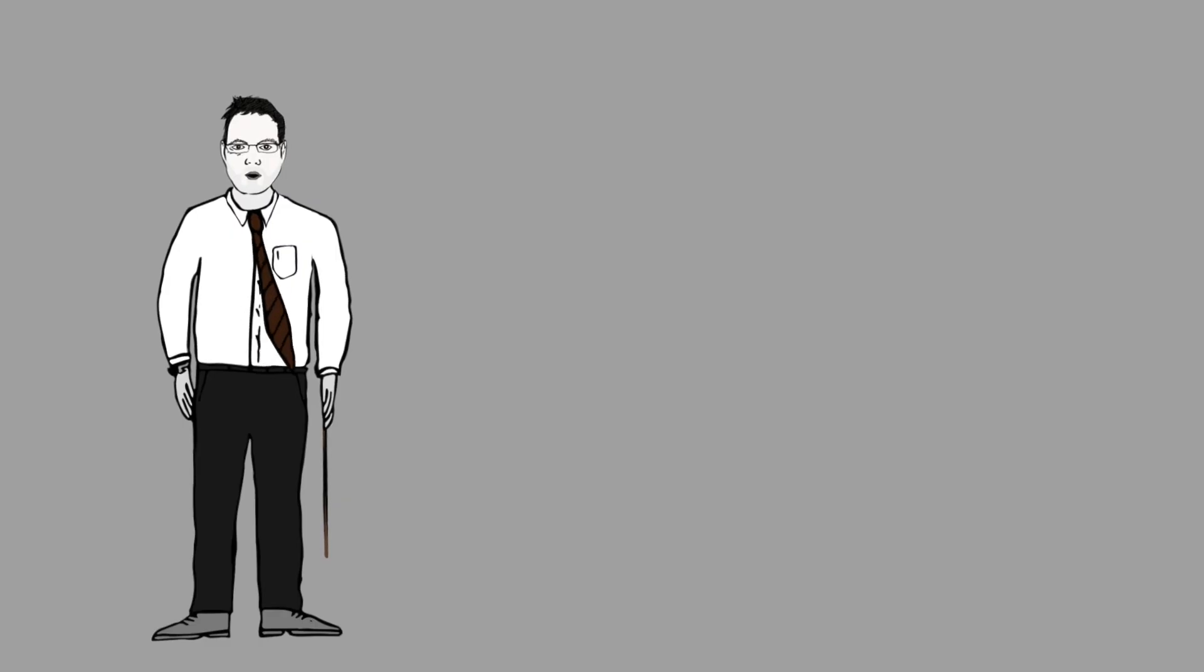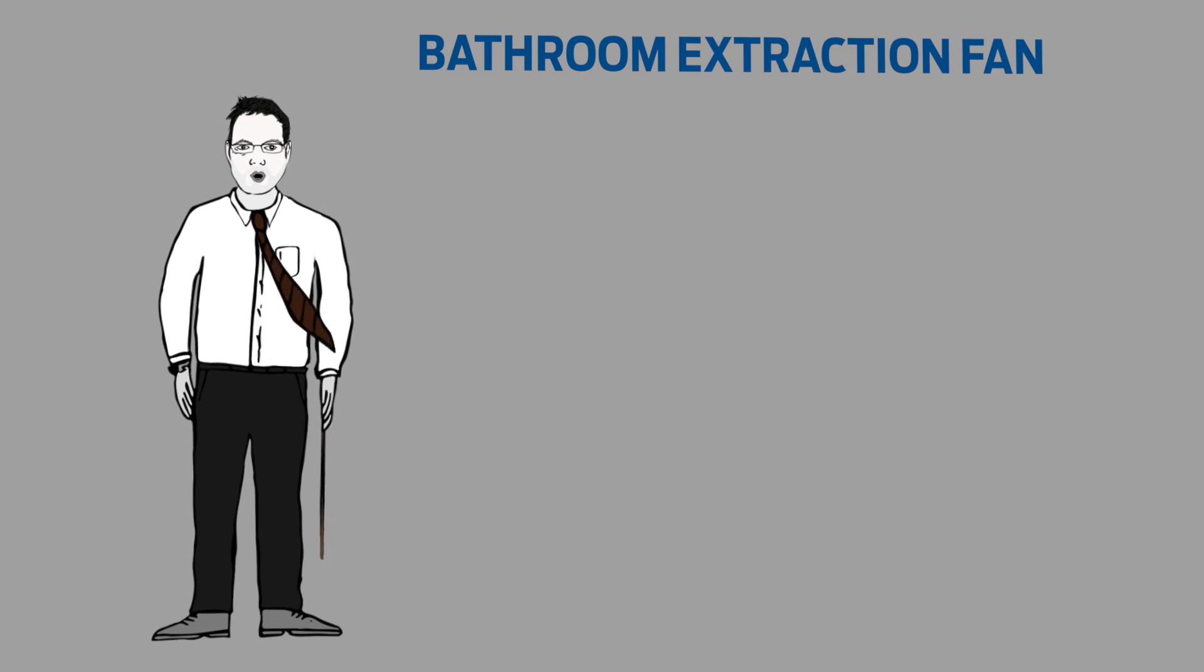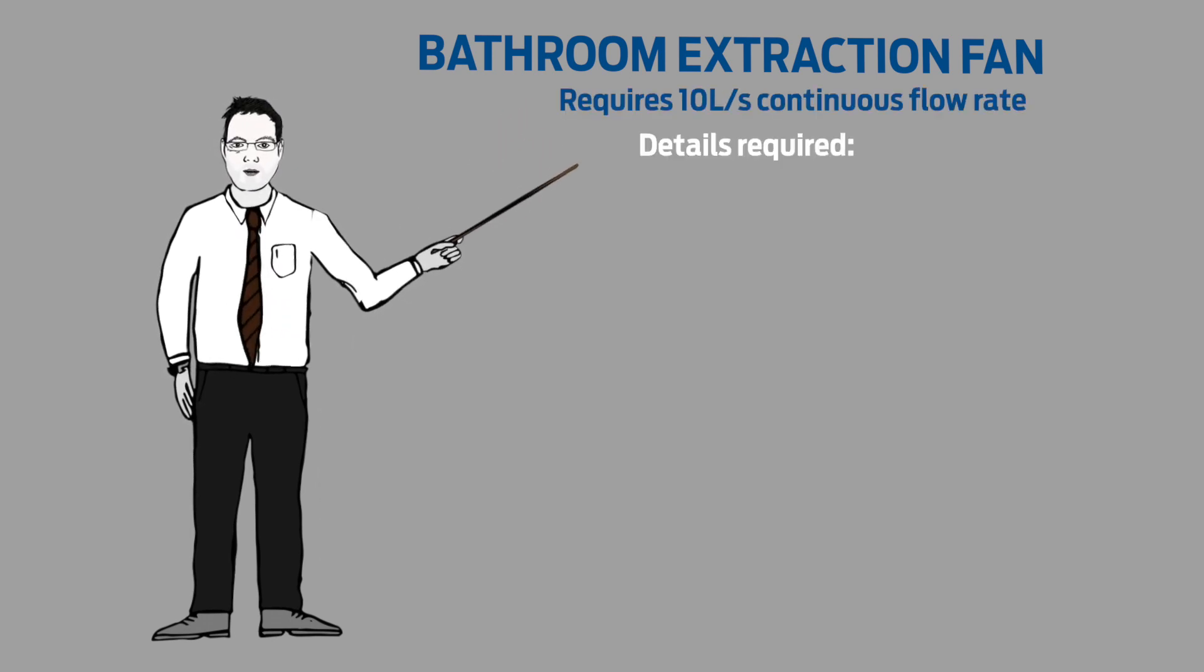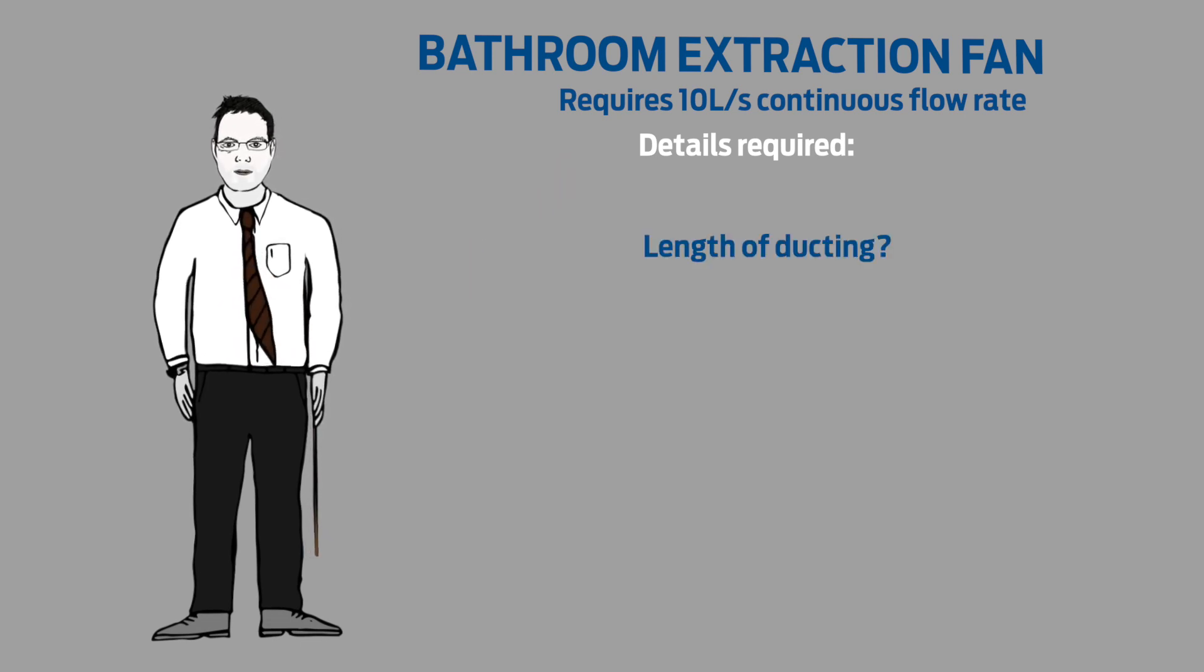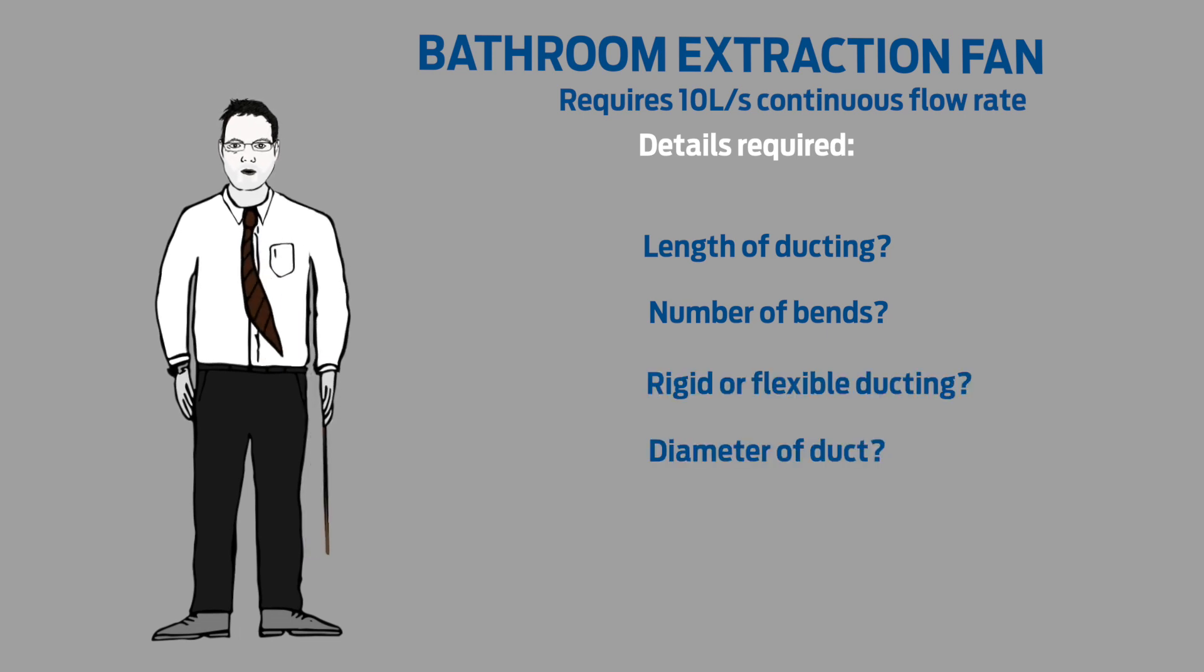Let's look at a worked example for a bathroom extraction fan. The standard lists 10 litres per second continuous flow rate for this case regardless of room size. In order to work this out we will need a few details: the length of any ducting required and the number of bends, and also whether we are using rigid or flexible duct and the diameter.